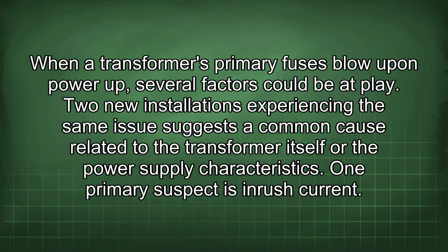When a transformer's primary fuses blow upon power up, several factors could be at play. Two new installations experiencing the same issue suggests a common cause related to the transformer itself or the power supply characteristics. One primary suspect is inrush current.